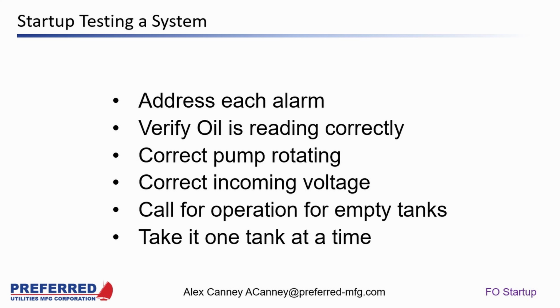I look at the alarm screen, and if I have any alarms, I address each one of them, either in the field or locally for the wiring, to make sure it is correct or incorrect, and make the corrections so that once you're ready to start, you have a totally clear alarm screen. Then you can start verifying that your oil is reading the correct level on the storage tank, because if you don't have a correct level reading there, you're going to get everything messed up when you start pushing fuel around.